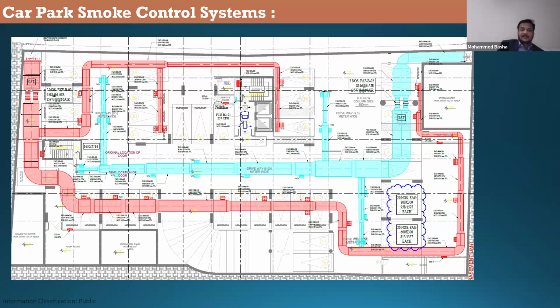You can reduce the duct size as much as you can, but do not go more than 10 meters per second, as it will have a very weird noise. So you are free to select the velocity as you require. You are not constrained here, because nowhere is it mentioned that the velocity should be within certain limits. If the extract is inside the building, passing through some occupiable space, that's a different case. But it's an open car park, and it is going to operate only in fire mode. So velocity is not a concern here, and you do not really need to have very huge ducts.